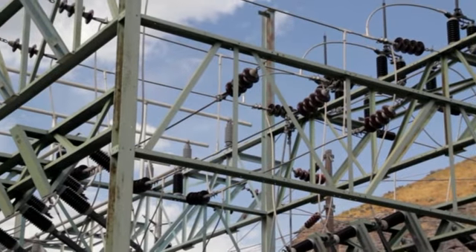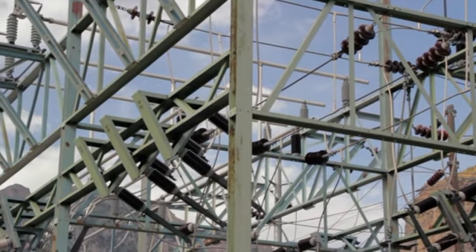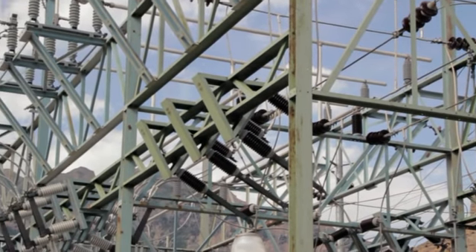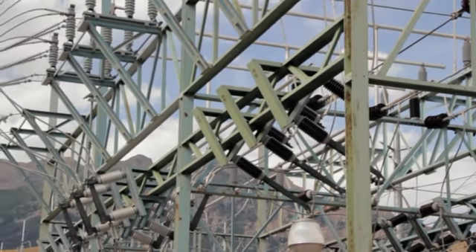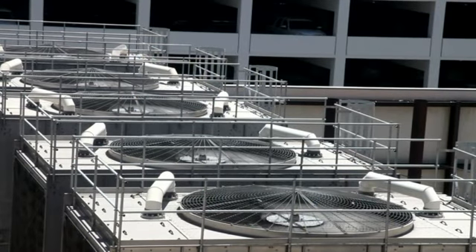A more common external generator of power surges is utility grid interactions. Utility substation switching and capacitor bank switching can put transients directly into the distribution system. Internally generated power surges are more common and account for 70% of all surges experienced by most facilities.